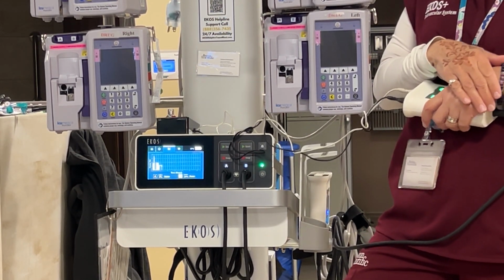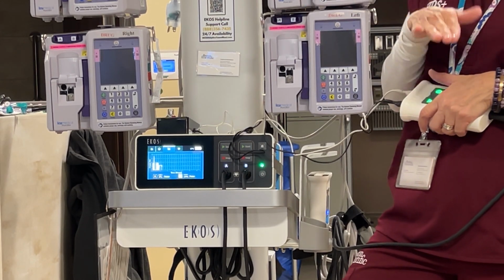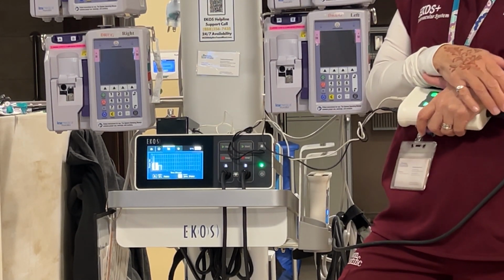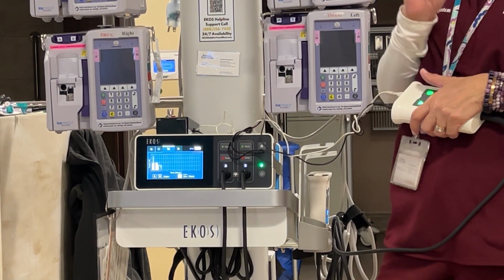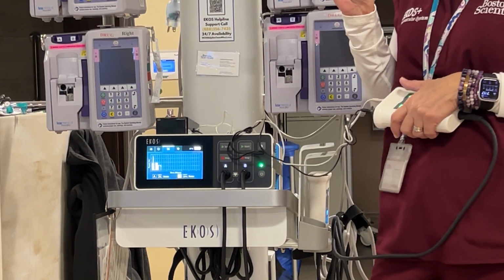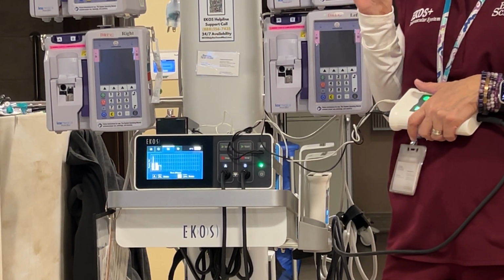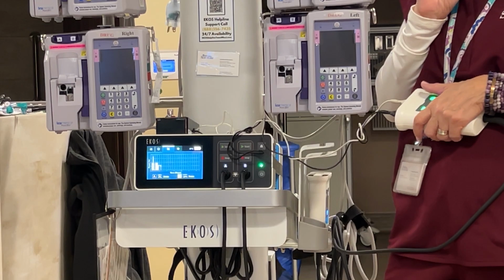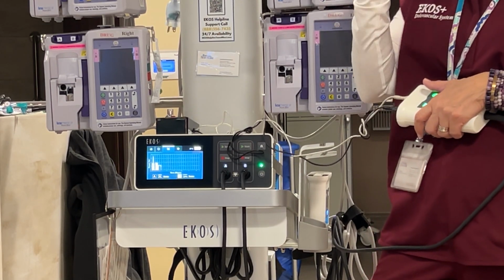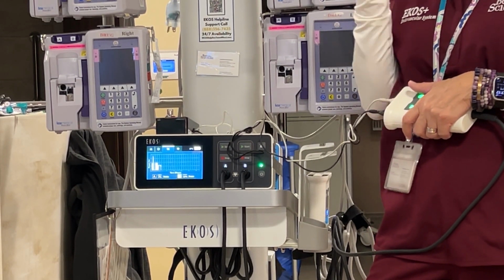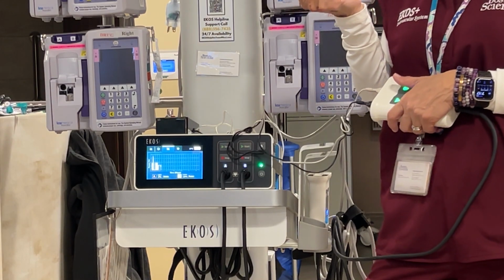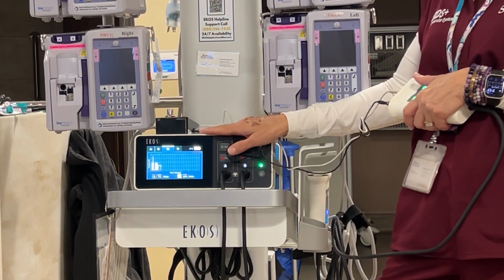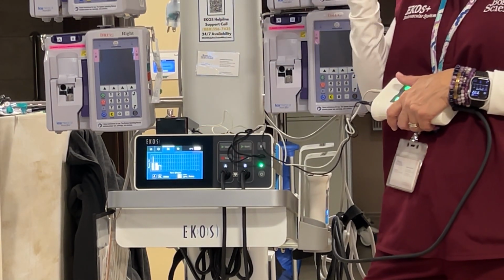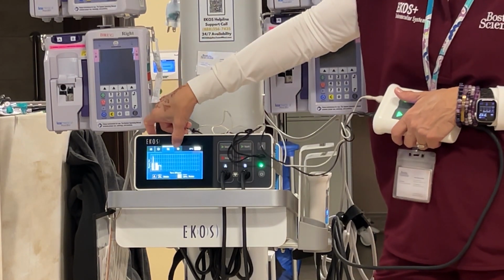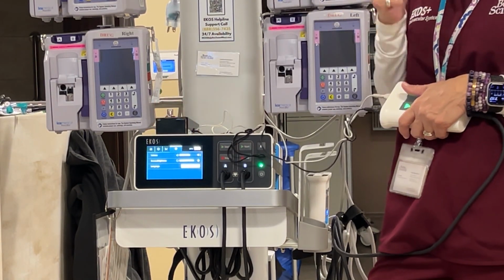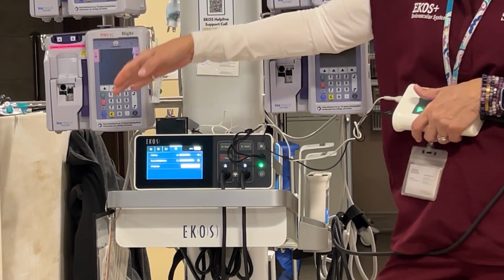When we are on battery power, the power levels actually drop down below 50% to conserve battery life. One catheter will run for 2 hours on a fully charged battery. 2 catheters will run for 1 hour on a fully charged battery. So whenever we transport, get to wherever we're going, we want to make sure it's plugged into a wall socket. We never plug this into a bed because it draws off too much power and will trip the breakers. Last tab is our settings tab. This is where you can adjust volume, screen brightness, and pick a language.